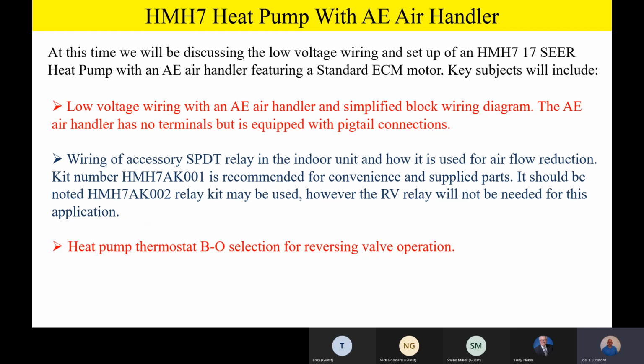It should be noted also on the HMH7, unlike our other heat pump products in our Champion lineup, the HMH7 utilizes the B terminal on the thermostat to energize the reversing valve in the heating mode. It's exactly opposite of all of our other heat pumps. It's not bad, it's just different. So please remember, your heat pump thermostat has to have a BO selection for reversing valve operation in the heating mode.